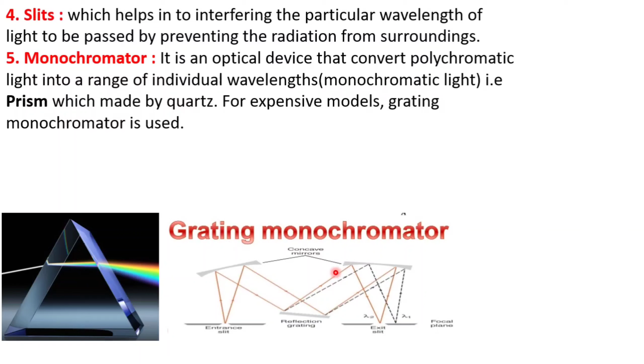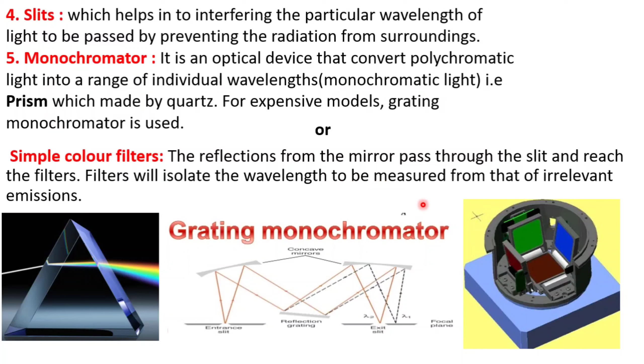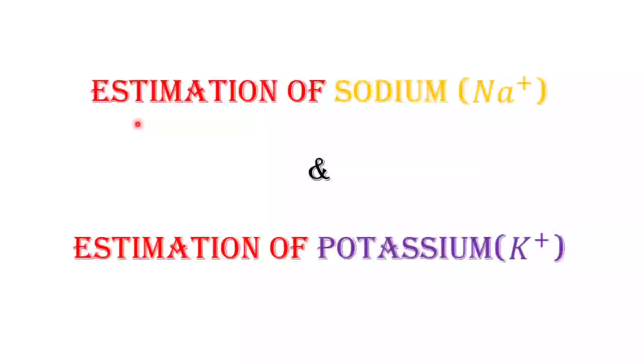For expensive models of flame photometer, grating monochromator is used. Here a series of parallel straight lines are cut in surfaces. In place of monochromator, we can use simple color filters. The reflection from the mirror passes through the slit and reaches the filter. Filter will isolate the wavelength to be measured from that of irrelevant emission.